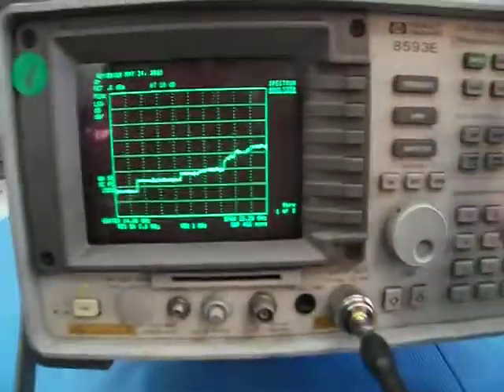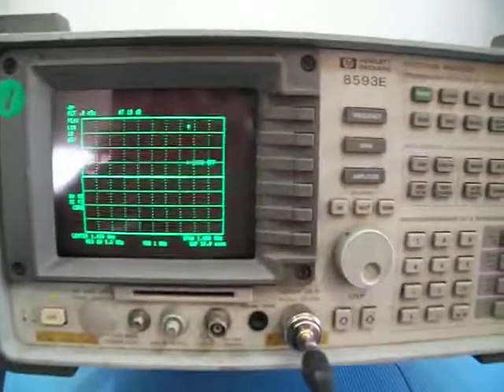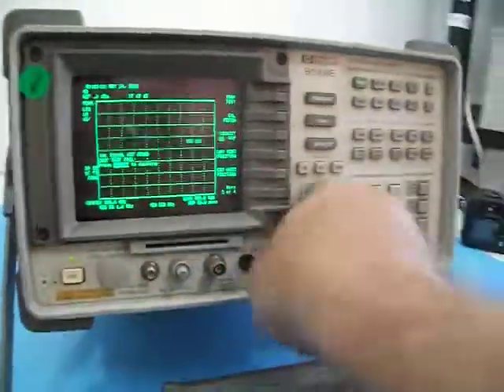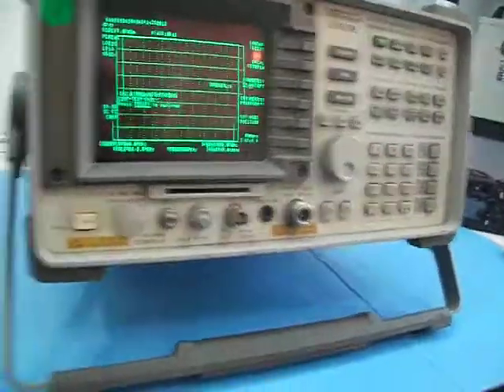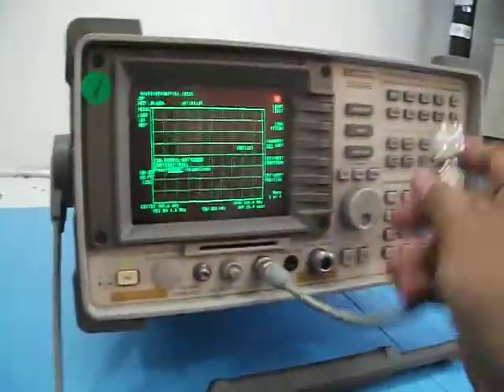Accurate, calibrated, and a very, very nice unit. This is the actual unit for sale. Let's do another test here — I'll turn it off and do a Cal confidence test. We check the unit. Cal signal not found — I need to connect here. For the confidence test, you need to connect the calibration signal.